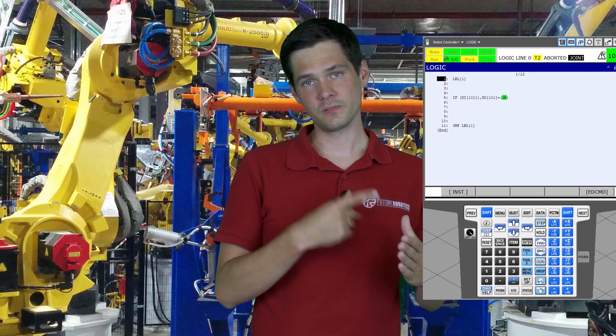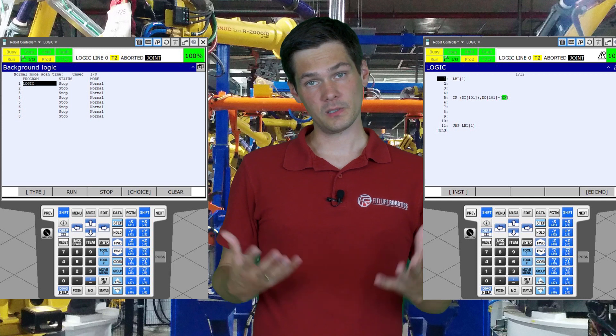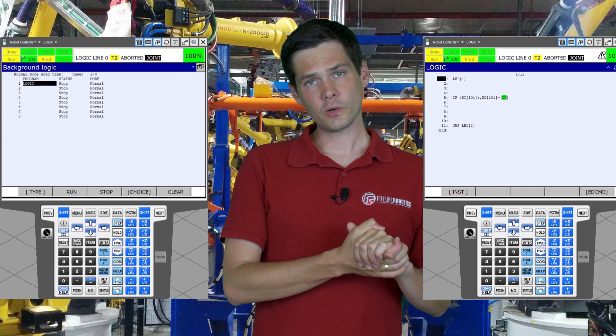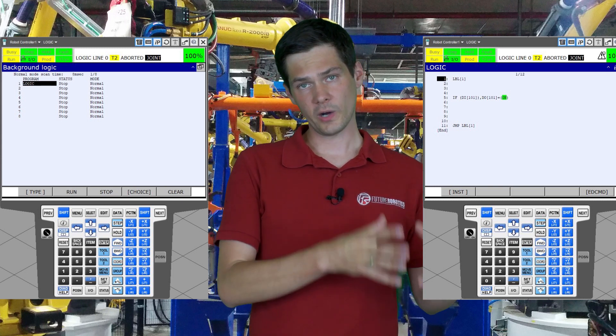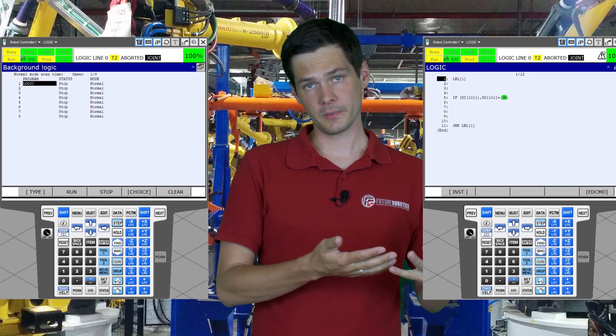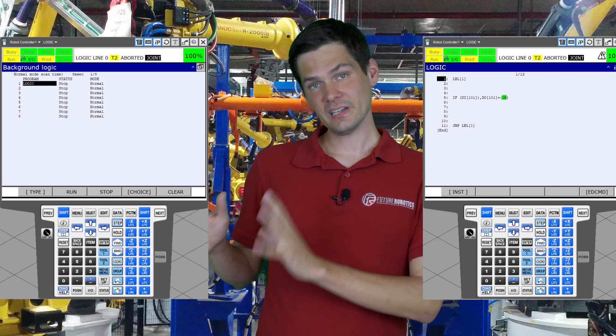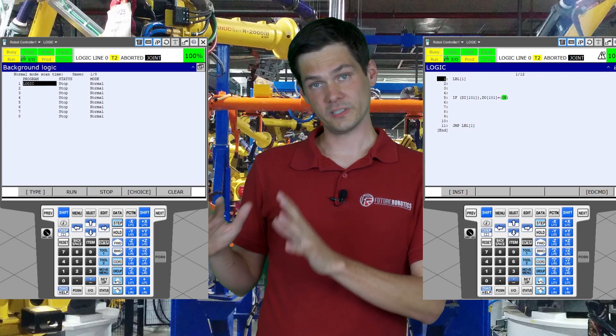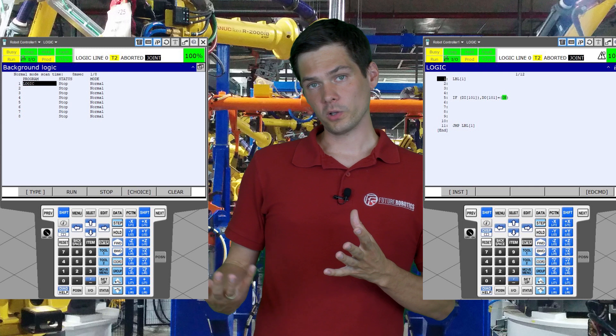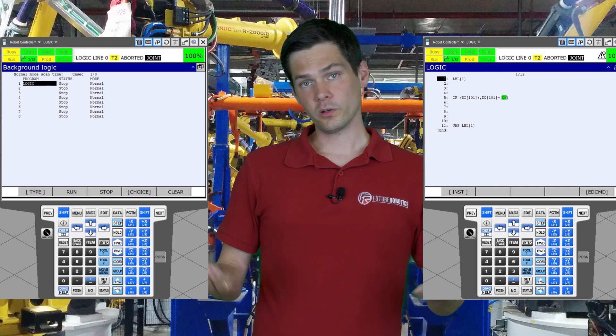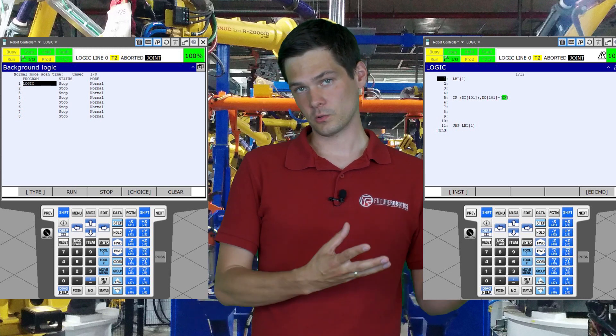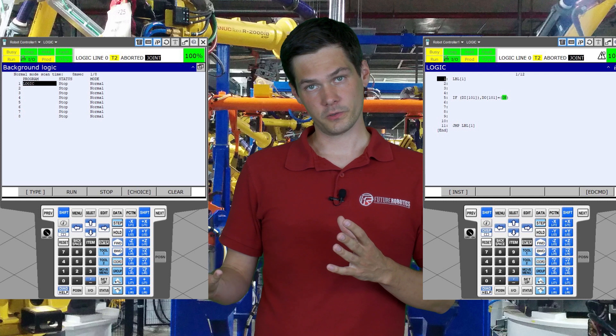So what is the difference between a program that you run with a jump label and the background logic? The jump-label program is going to run only when a program is actually executing. The background logic doesn't care about whether a program is running or not — it runs all the time. So if you want to monitor something constantly or notify the PLC even though the robot isn't running, you want to use the background logic.